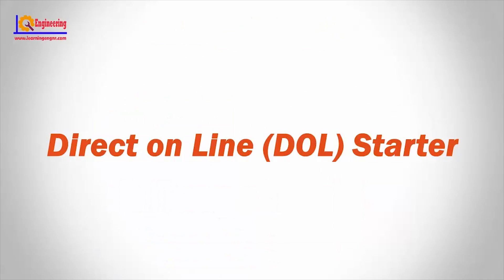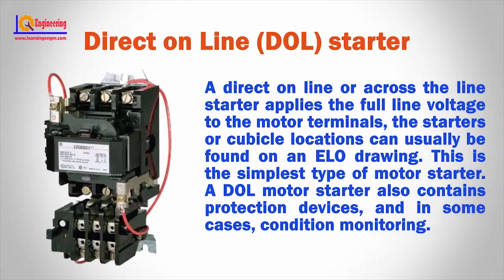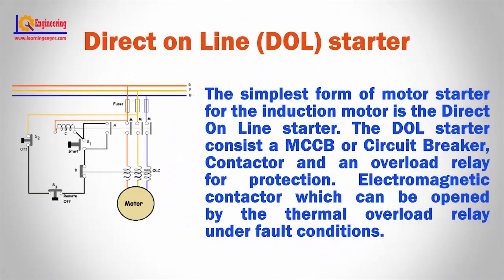Direct online DOL starter. A direct online or across-the-line starter applies the full line voltage to the motor terminals. This is the simplest type of motor starter. A DOL motor starter also contains protection devices and in some cases, condition monitoring. The simplest form of motor starter for the induction motor is the direct online starter. The DOL starter consists of a MCCB or circuit breaker, contactor, and an overload relay for protection.